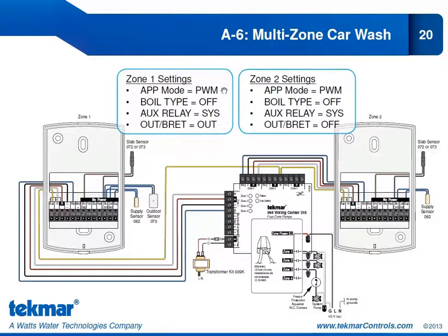Our application mode is PWM, and that holds true for both Zone 1 and Zone 2. Now this is a multi-zone system. That is why we are going to use application mode PWM. You can also use the method of elimination. None of the other application modes fit. But multi-zone systems, we do want to use PWM.